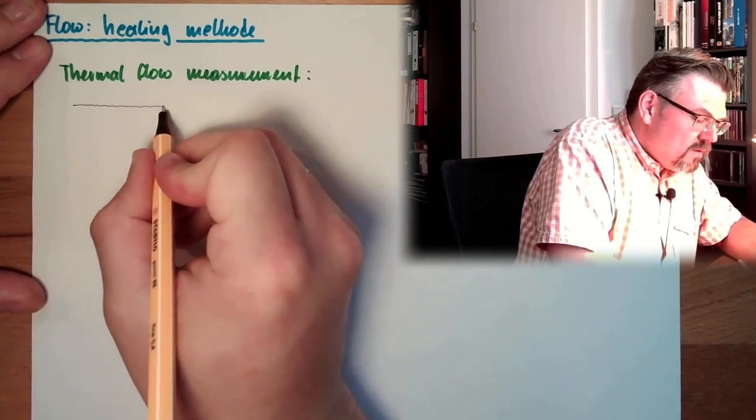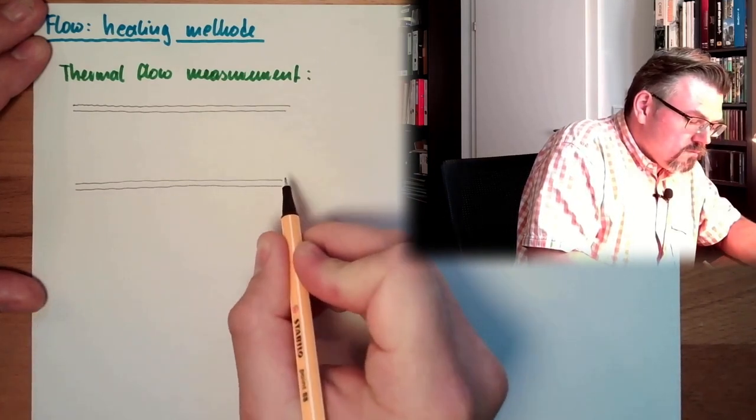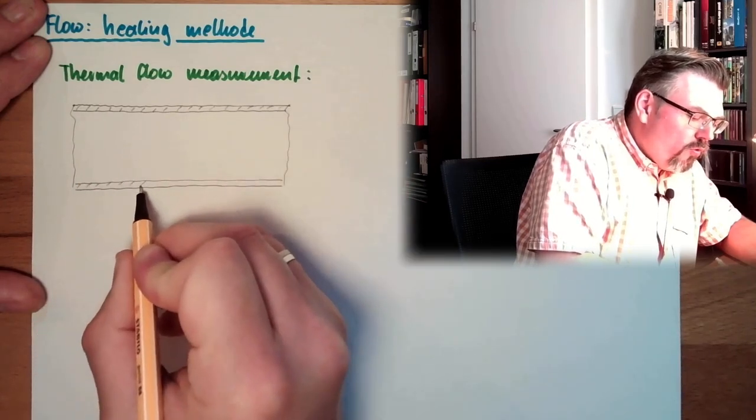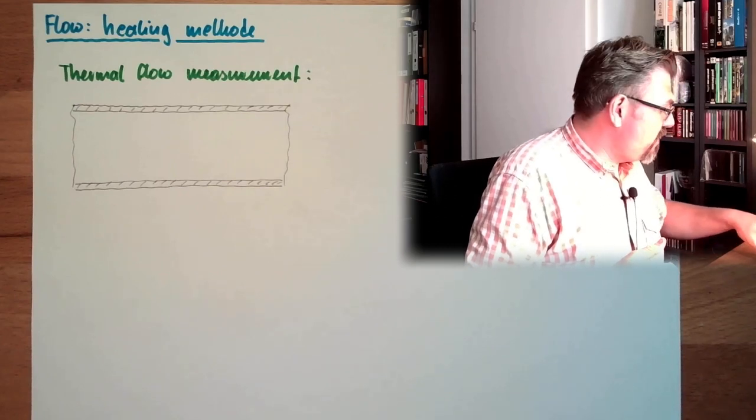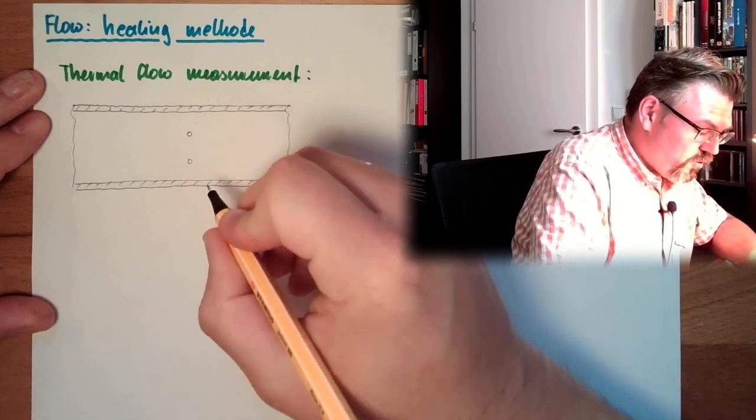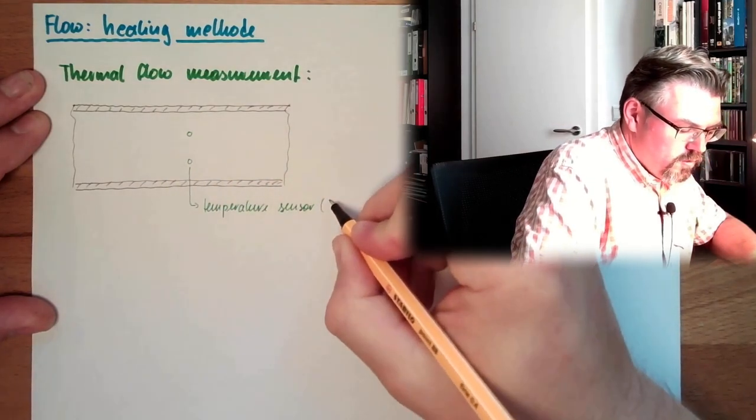Let's first have a look at the thermal flow measurements. So we again have a tube or something like this where our medium is flowing. It can be liquids, it can be gases. And inside this tube I am placing two thermal measuring points, two usually PT100. We talked about temperature measurement. So we have here a probe, another probe, temperature sensor probes, usually PT100.